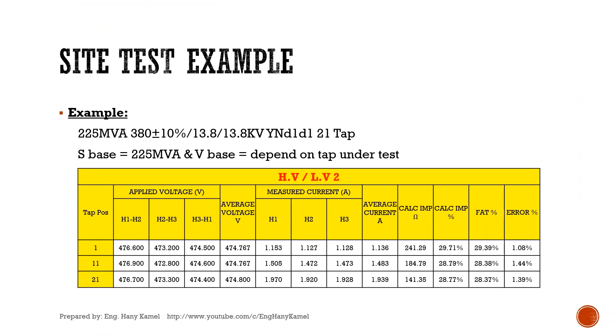The same test procedure will be done, but with the second low voltage winding shorted and the first low voltage winding opened, injecting from the high voltage side. The results and the calculated errors are shown for the high voltage winding and the second low voltage winding.